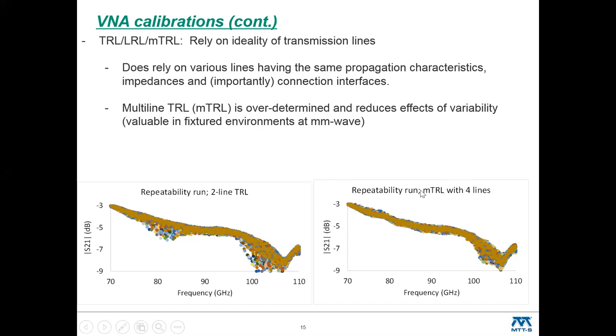The same approach was done with a four-line calibration, and the divergence was noticeably less in that case. So this is a moving trend in the higher frequency calibration world—the downside being, of course, that you need more standards.